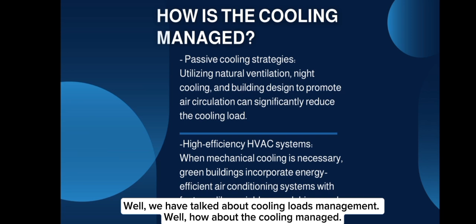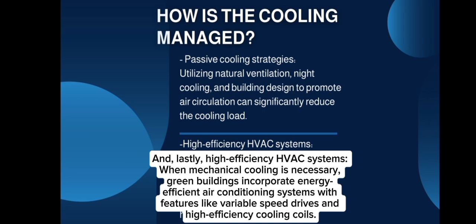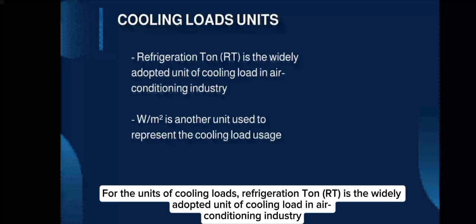We've talked about cooling load management. Now how is cooling managed? First, passive cooling strategies, utilizing natural ventilation, night cooling, and building design to promote air circulation, can significantly reduce the cooling load. Lastly, highly efficient HVAC systems: when mechanical cooling is necessary, green buildings incorporate energy-efficient air conditioning systems with features like variable speed drives and high-efficiency cooling coils. For the units of cooling load, refrigeration tonne (RT) is the widely adopted unit in the air conditioning industry, while W/m² is another unit used to represent cooling load.